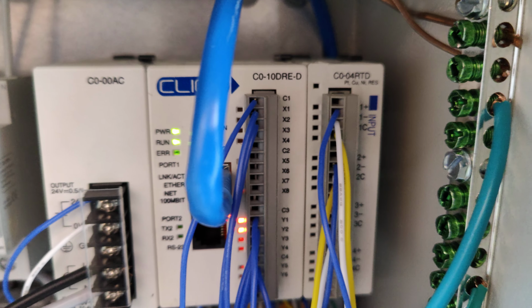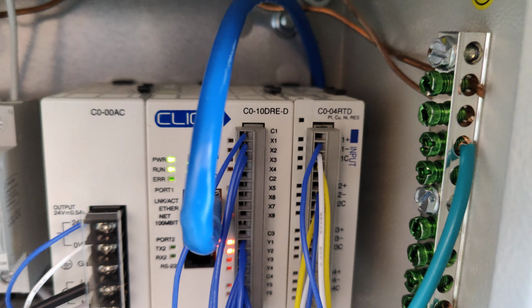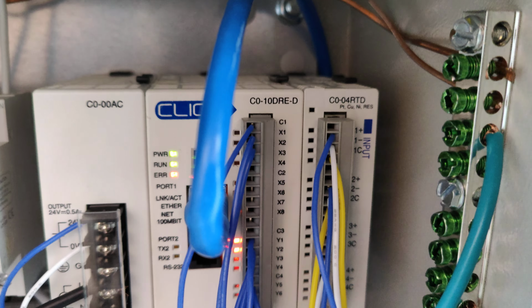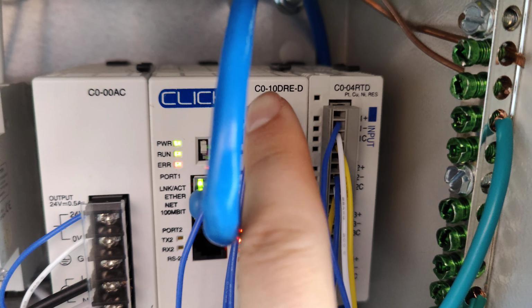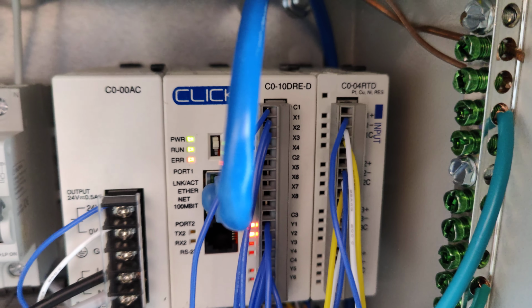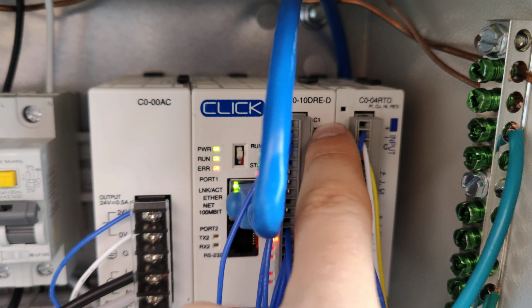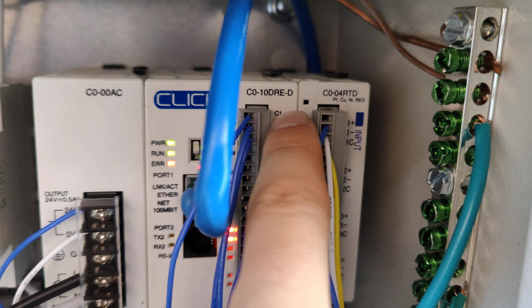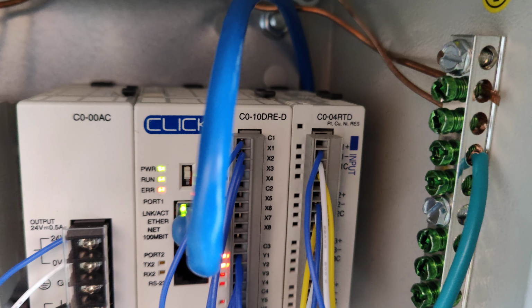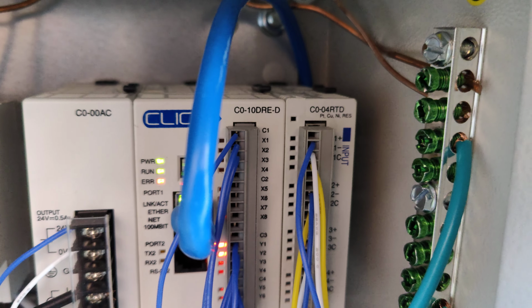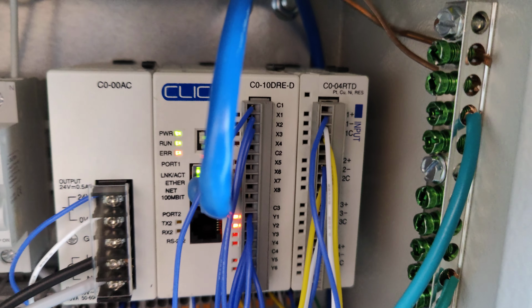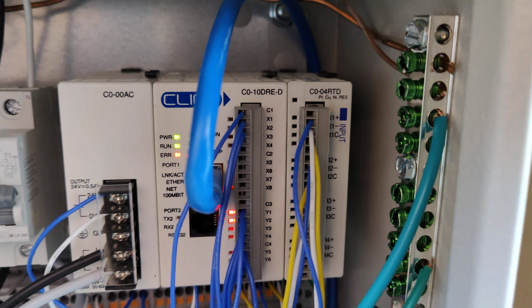So I don't have any other inputs here except for this temperature probe on that side, but I don't have any inputs here. So I didn't know what polarity or what common wire to wire this to, if I wire that to a negative, the common to a negative, or the common to a plus. So a good way to test, and what I always do, because you can do this for 24 volts, is...